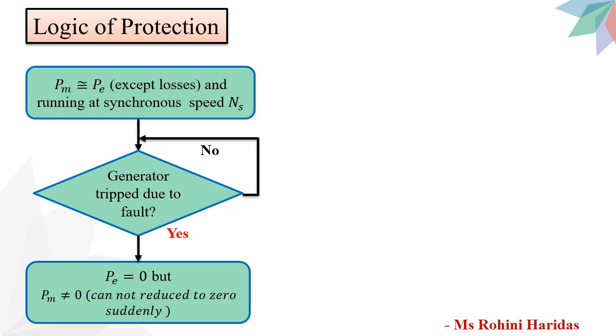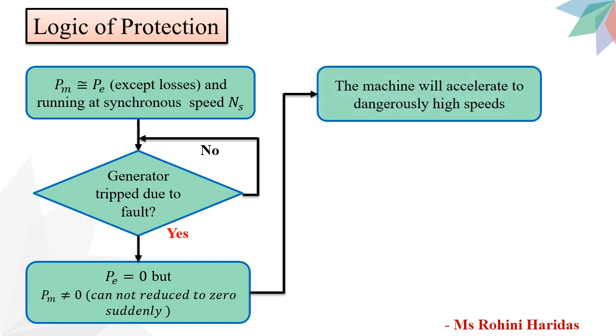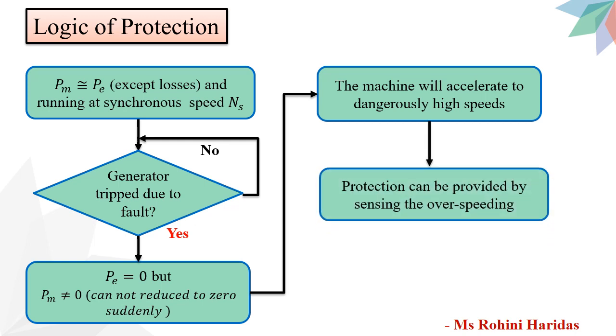However, the mechanical power input PM cannot be suddenly reduced to 0. Therefore, we land up in a situation where the generator has full input mechanical power but no output electrical power. This would cause the machine to accelerate to dangerously high speed if the mechanical input is not quickly reduced by the speed governing mechanism. Protection against such a condition can be provided by sensing the overspeeding and taking steps such as operating the steam valve so as to stop the input to the turbine.